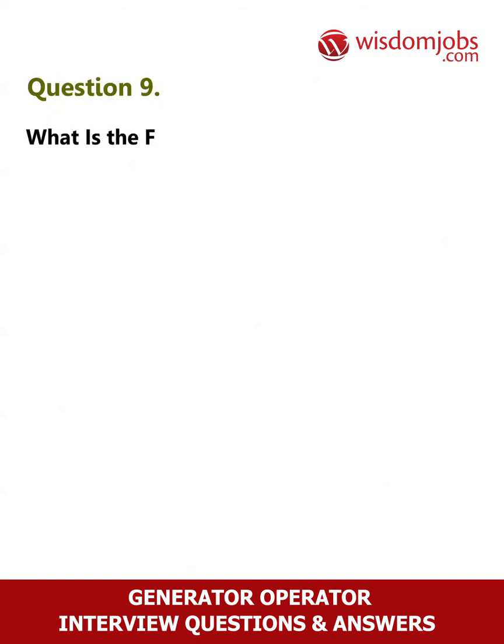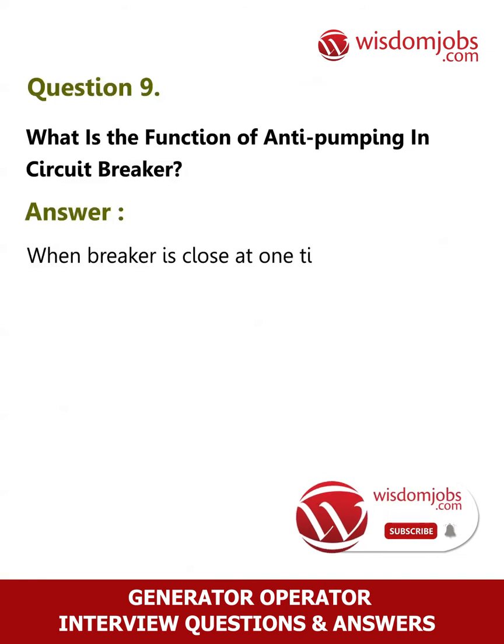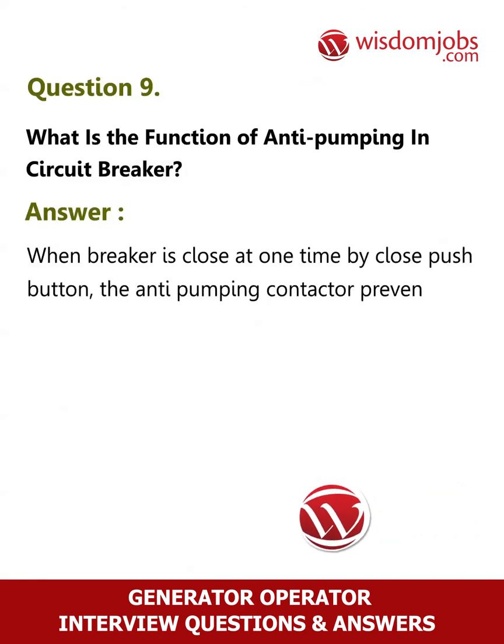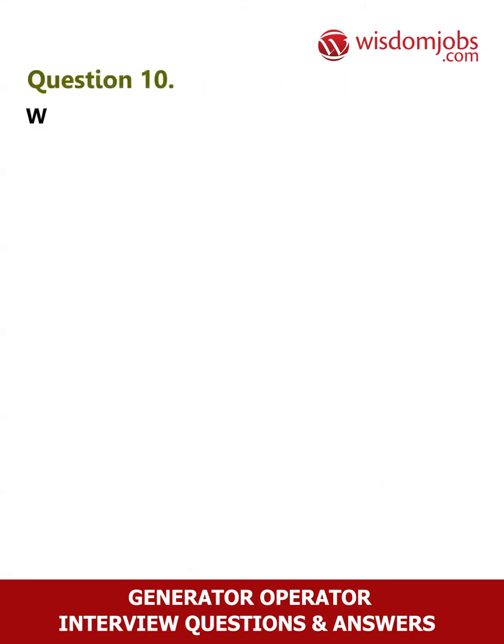Question 9: What is the function of anti-pumping in a circuit breaker? Answer: When the breaker is closed one time by the close push button, the anti-pumping contactor prevents re-closing of the breaker by the close push button after it is already closed.